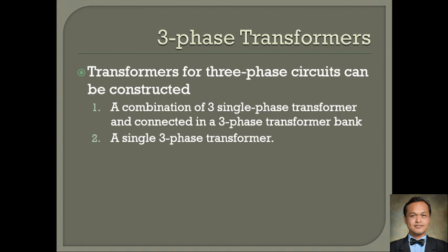Now, the advantages and disadvantages of these setups: if you use a combination of single-phase transformers as a three-phase transformer, the cost of a single-phase transformer is much cheaper than a single three-phase transformer. And if there is an imbalance in the system, in the combination of transformers, only the damaged one will be replaced.